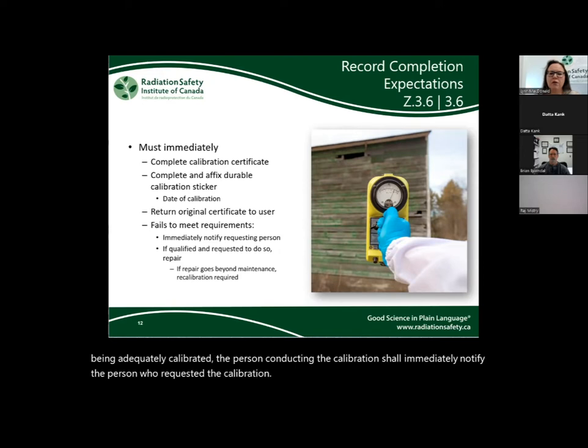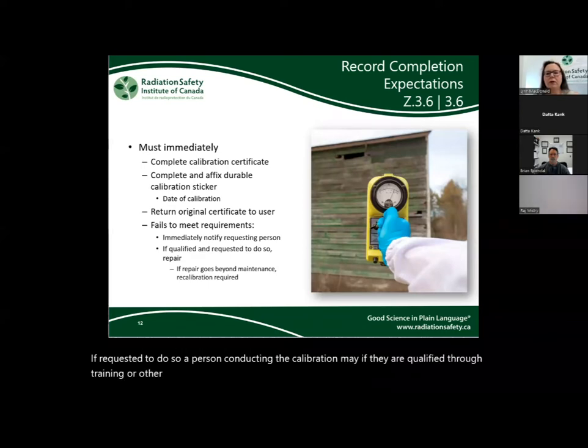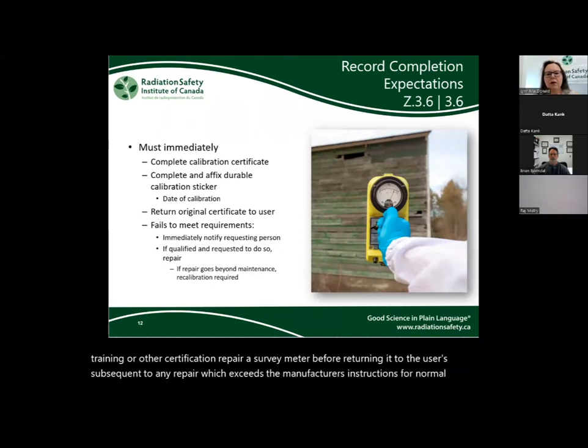If requested to do so, a person conducting the calibration may, if they are qualified through training or other certification, repair a survey meter before returning it to the user. Subsequent to any repair which exceeds the manufacturer's instructions for normal maintenance, a survey meter must be recalibrated.